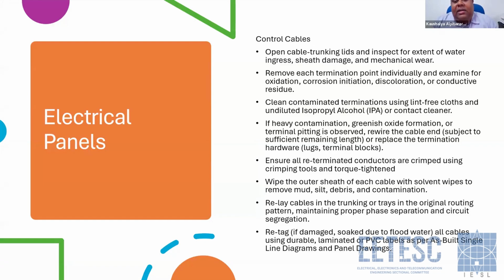Control cables and all: remove all the trunking, and check for mechanical and electrical damage. If possible, rewire, and minor damages could be restored, especially if the water ingressed through the sheath of these small stranded cables. Those will be oxidized and will eventually get damaged. All other control parts, indicators and all, will have to be replaced.